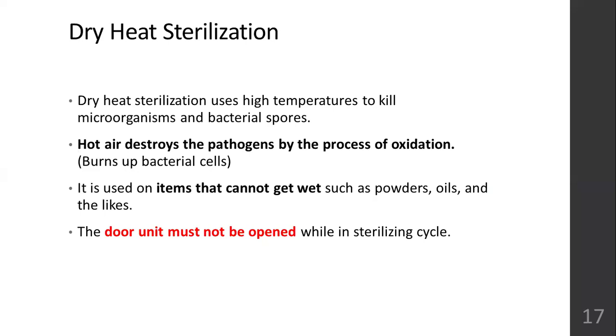Then dry heat sterilization, it uses high temperature to kill microorganisms and bacterial spores. Hot air oven and all. So hot air burns the cells of the bacteria. That is what the hot air does here. It burns the bacterial cells. That's how it destroys the pathogen. Some spores it cannot destroy, but the majority of the spores can be destroyed here. So it should be used.